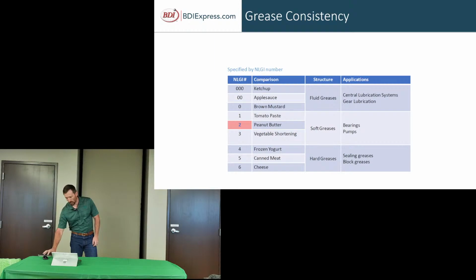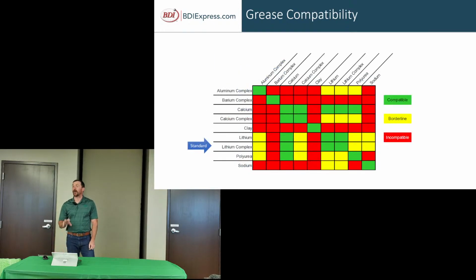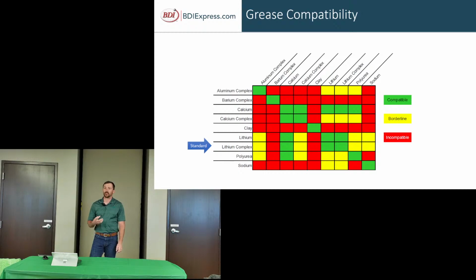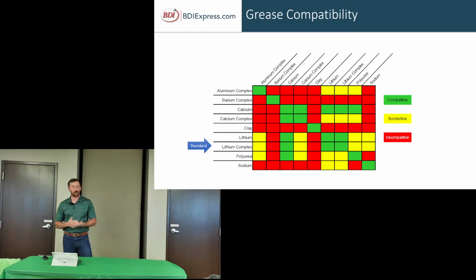And then how I mentioned before, mounted bearing grease versus motor bearing grease. Do not mix the two. I know this chart says it's borderline compatible, but mixing a lithium complex grease with a polyurea, that is going to cause that grease to almost turn into a clay. And that's the harder that bearing has to work in either your motor or your mounted bearing. It's going to cause it to increase your heat, which is going to cause bearing failure in your motor or in your mounted bearings.